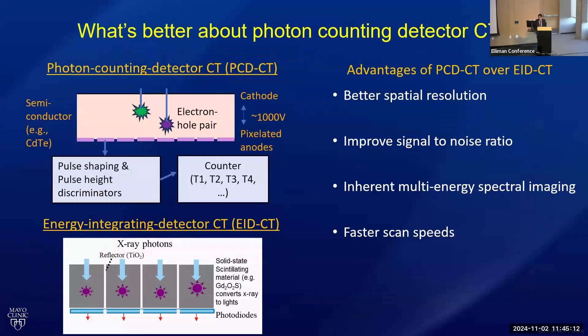How is that different from photon counting CT? Most of it is actually the same — the x-ray source is the same, the tube is the same. Really the only difference is the detector and how the x-rays are detected. In traditional CT scanners, called energy integrating detector CT, the x-rays encounter the detector and through a two-step process are first converted to visible light photons, then converted to an electrical signal. The light photons have to get summed up, so you don't actually count every photon that hits the detector and you lose some energy information. In photon counting CT, the x-rays hit the detector and are immediately converted to an electrical charge, which is read out by the detector — so every photon gets counted, giving us more information and producing better images.